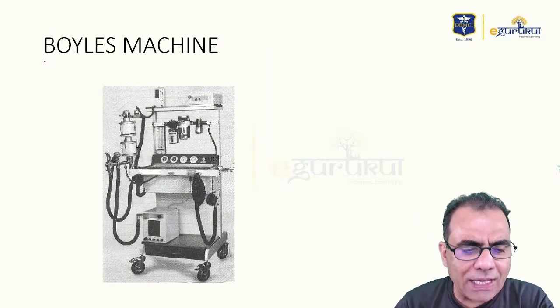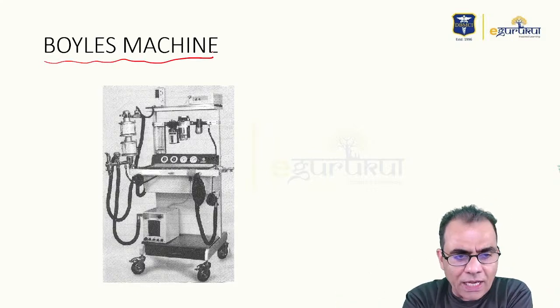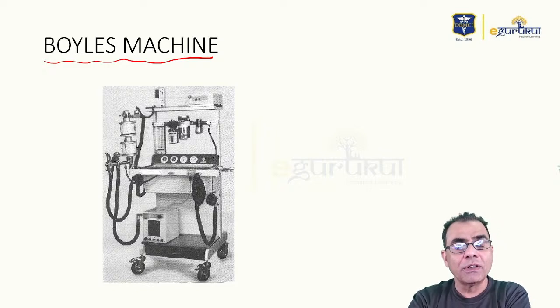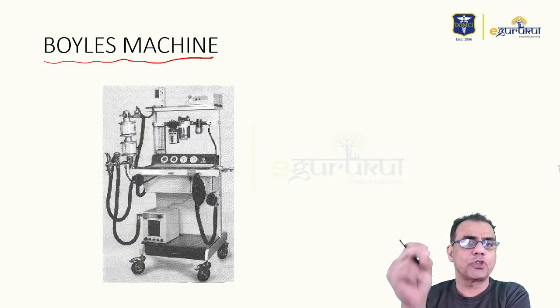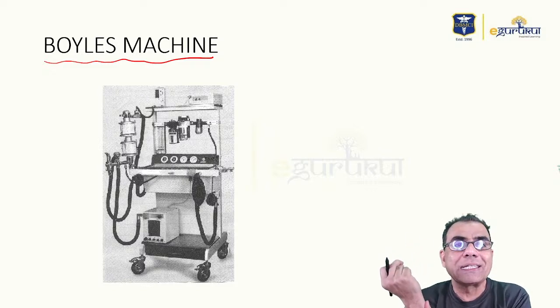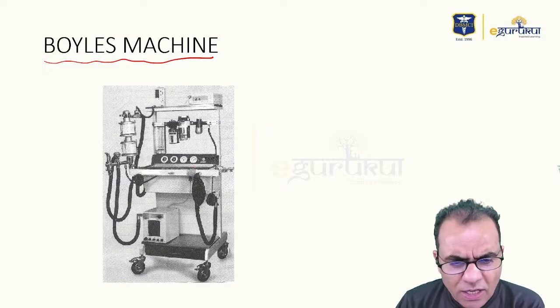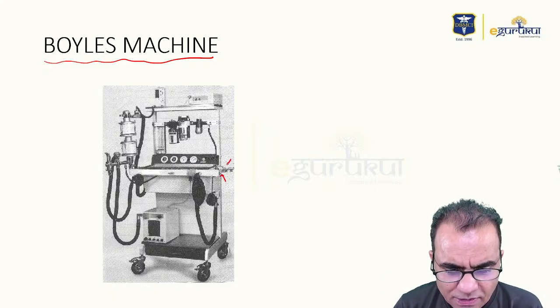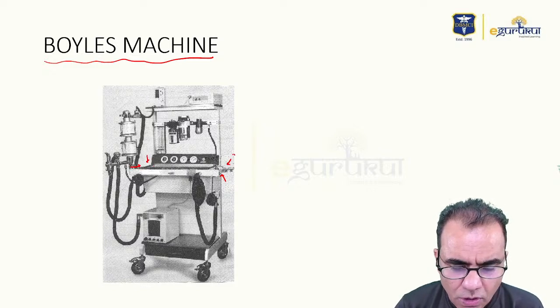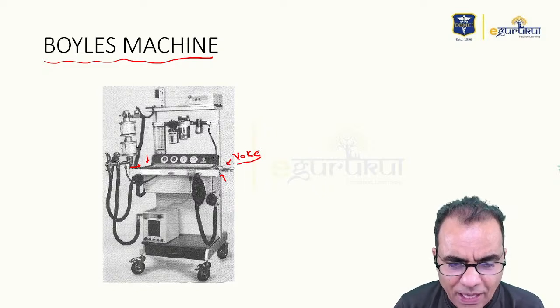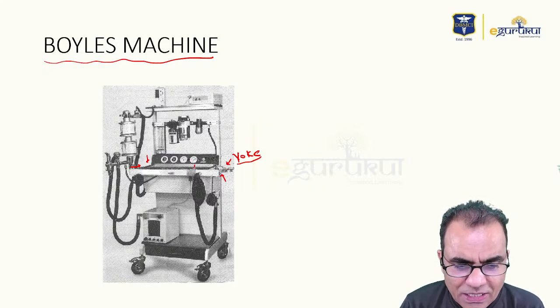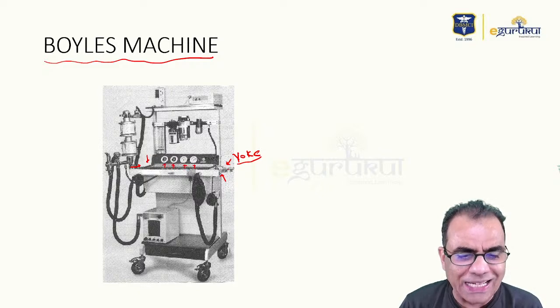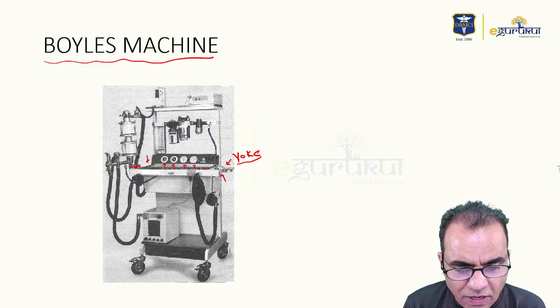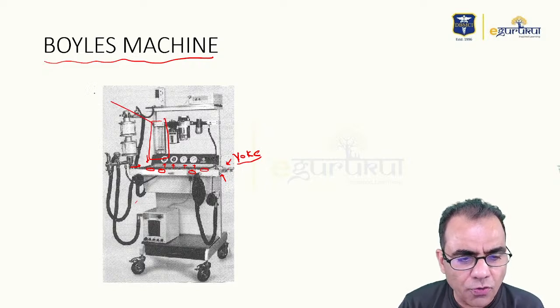So this is the old anesthesia machine, and you know that in older times the anesthesia machine used to be called Boyle's machine. Why? Because the first anesthesia machine was manufactured by a scientist called Boyle. So this is the Boyle's machine. You can see this is the yoke. Obviously the cylinder or central supply will be fitted here. And these are the pressure gauges which tell you how much is the pressure in the central supply or cylinder. Then there will be pressure reducing valves inside. You cannot see them from outside, they are the inside part. After this pressure reduction, gases will pass through this rotameter. So this is of course the rotameter.